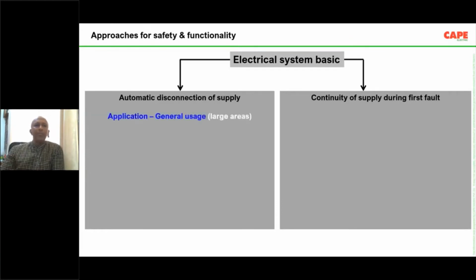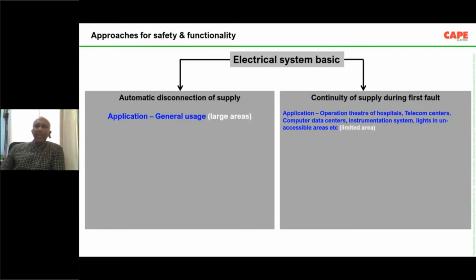The first case we use for a general application, and the second case we are supposed to use for special applications, say for example, operation theaters in hospitals. Because imagine there is an operation theater and some activity is going on, and if the incoming MCB trips, what is going to happen? This will become a disaster. So for certain applications, disconnection of the supply is dangerous, and for those applications, continuity of supply is highly important. So as I have written here, this is the continuity of the supply.